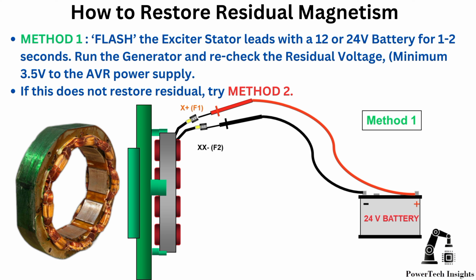Method 1. Flash the exciter stator leads with a 12 or 24V battery for 1 to 2 seconds. Run the generator and recheck the residual voltage, minimum 3.5V, to the AVR power supply. If this does not restore residual, try Method 2.